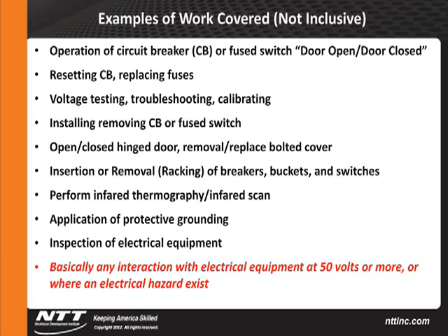Insertion, removal, racking of breakers. Perform infrared thermography. Many people call it infrared scanning. Application of protective grounding, putting them on, taking them off. Simply the inspection of the electrical equipment. How many places do I go into that they ask me, there's an engineer, an electrical engineer, opening up a cabinet, is that covered by the standard? The answer is yes. They're inspecting it, they're doing it. Things can go wrong.